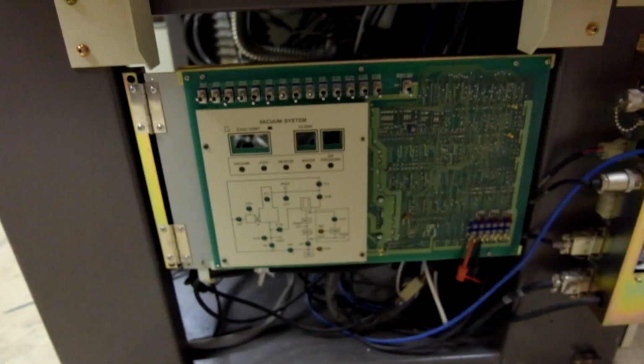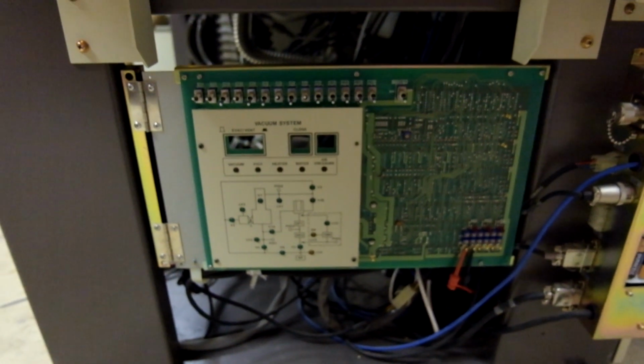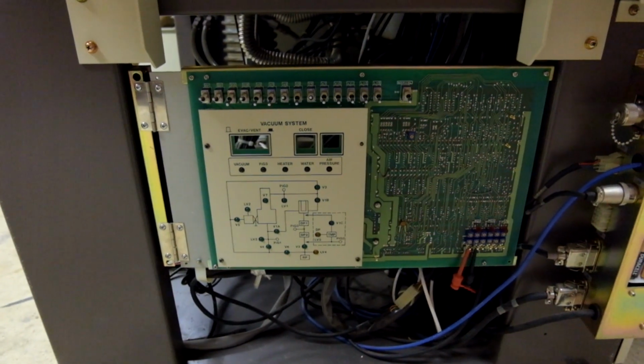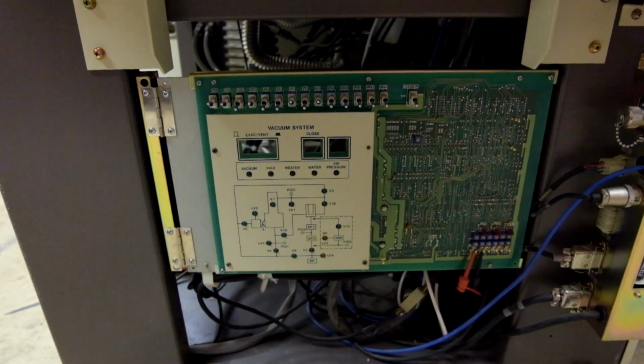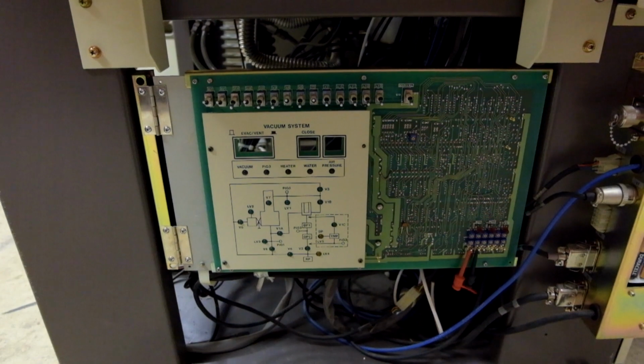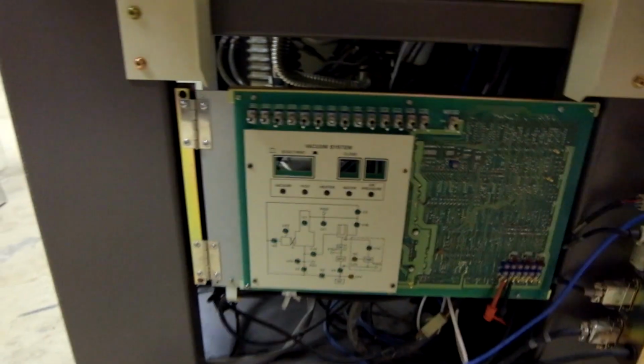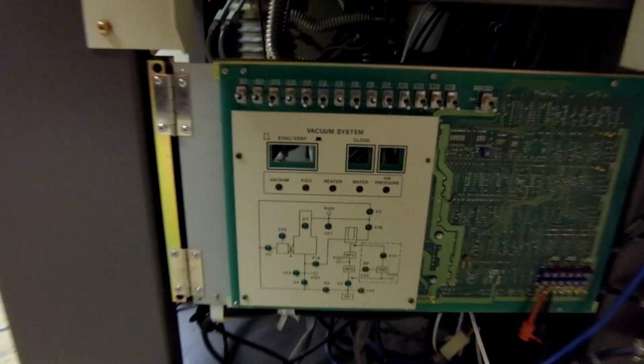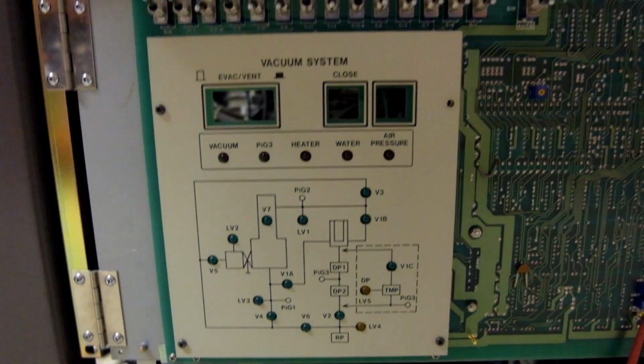And this is the back of the vacuum control board, which I'm having some issues with, so I have the front panel off as well. This thing is supposed to automatically control the vacuum system, so when you turn the microscope on, it should rough the main chamber and then evacuate it down with the diffusion pumps automatically. But it's having some issues, so I have to do it manually by flipping all these switches and looking at this cool diagram here. So that's a little bit annoying, but it's not that big of a deal.